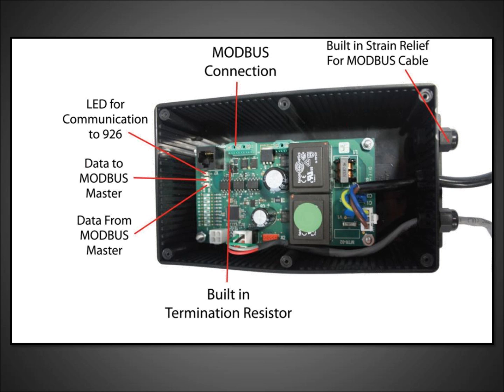We have a built-in termination resistor. We have a ModBus connection. You can see that connector is a 3-wire connector, which we'll explain a little bit more as we go along. And then what we did is we put strain reliefs in there for just ease of facilitating wire connection for the customer.